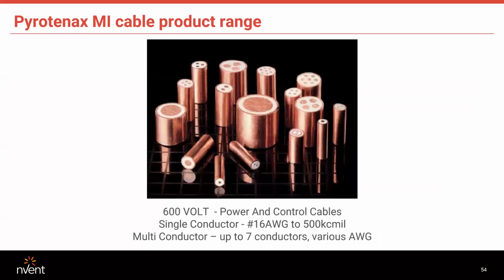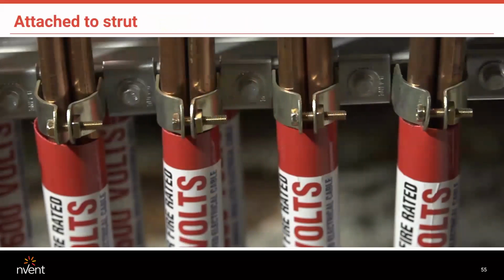And we come in a wide variety of sizes: 600 volt, single conductor, 16 to 500 kcmil, and multi-conductor cable. Our largest multi-conductor is probably a number 4, 3 conductor, and we do go up to 7 conductors in certain sizes. But with the larger size cables, we generally use multiple runs of single conductor. I'll show you a few photos we have here.